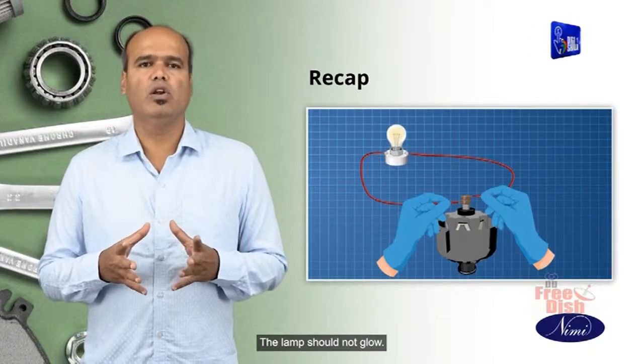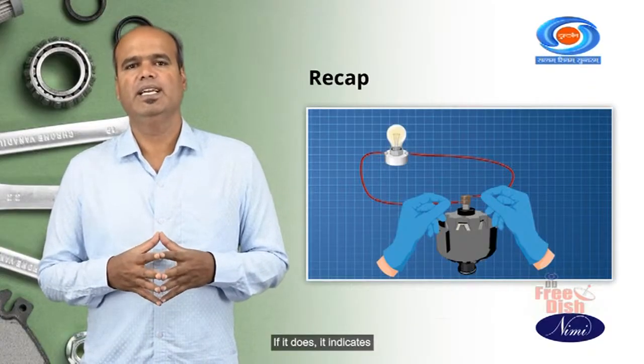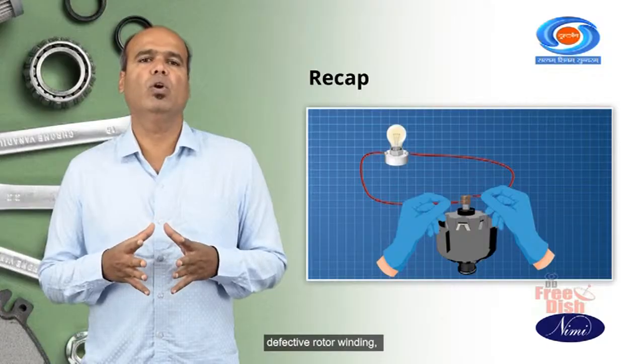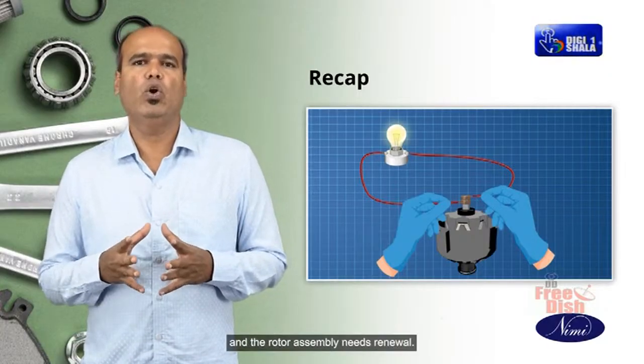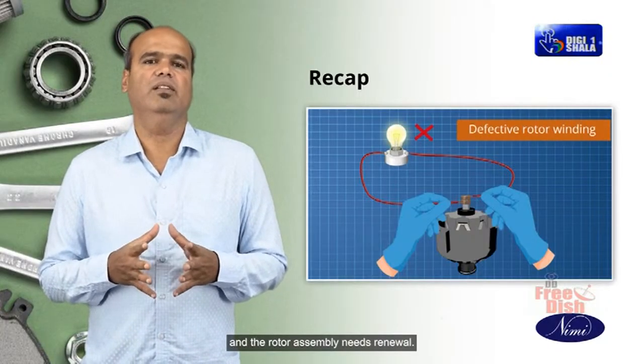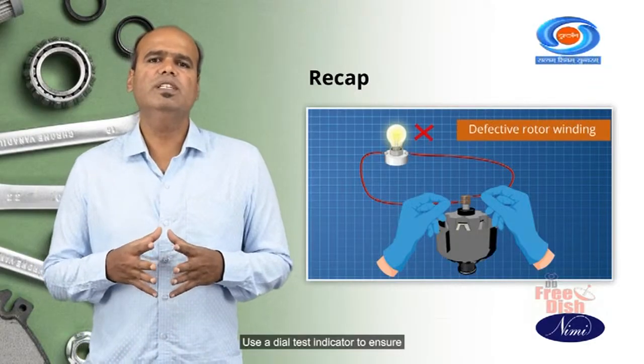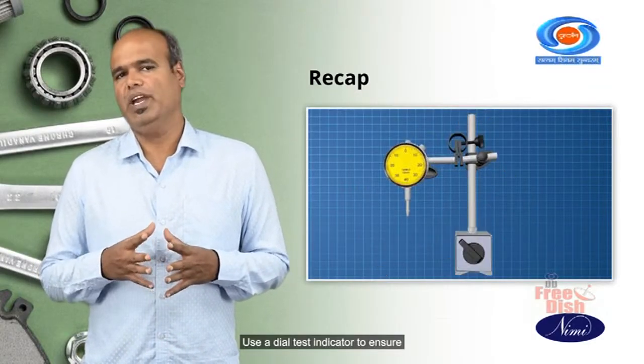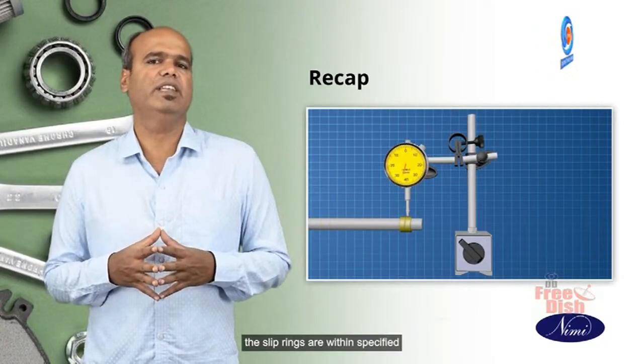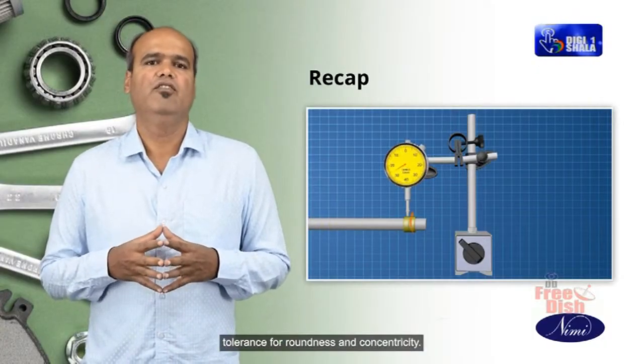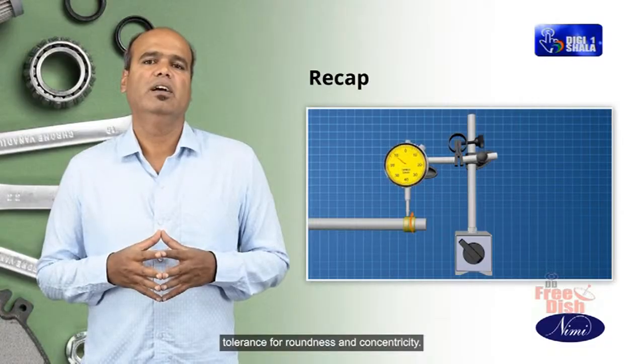The lamp should not glow. If it does, it indicates defective rotor winding and the rotor assembly needs renewal. Use a dial test indicator to ensure the slip rings are within specified tolerance for roundness and concentricity.